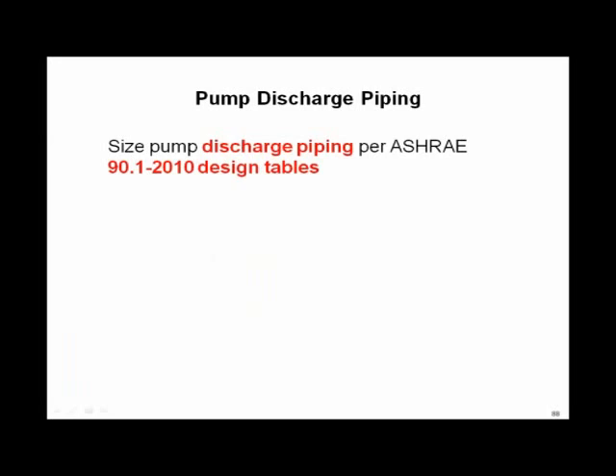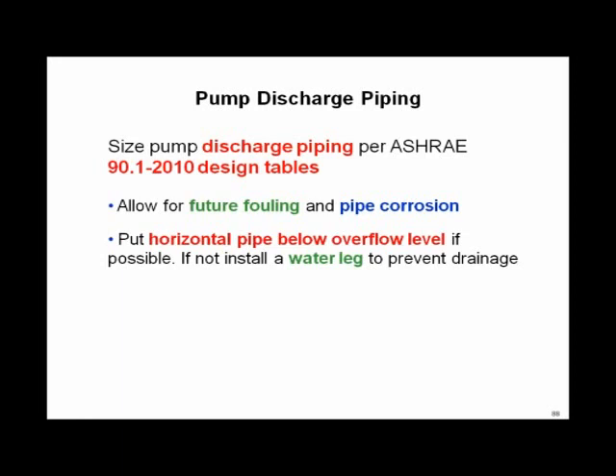Now, let's look a little bit at discharge piping. First of all, you saw that ASHRAE 90.1 2010 now defines the minimum pipe sizes on condenser water piping, so you might as well get used to it. You do need to allow a little bit for future fouling and pipe corrosion. What's a reasonable number? You decide. A 5 to 10 feet safety factor is what I see people normally doing. It is reasonable to assume that in an open system like a cooling tower, the piping over its pipe life is going to foul some and you will pick up a little additional pressure drop.